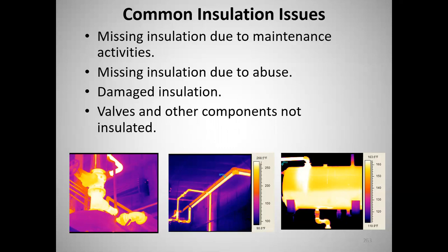But what they did, they went to Lowe's, and you can buy this straight insulation that's split, and you just clip it on the pipe, which is fine. And they did that. They didn't insulate the elbows. Or you can get insulation with the elbows, but they said, we're not going to worry about that. So all of the straight pieces had this on it. And if you shot it with the camera, it was all dark, and all of a sudden the elbow was there, and the fitting, and the T, and all this stuff. To be honest with you, it looked like hell, but it was insulated pretty well.